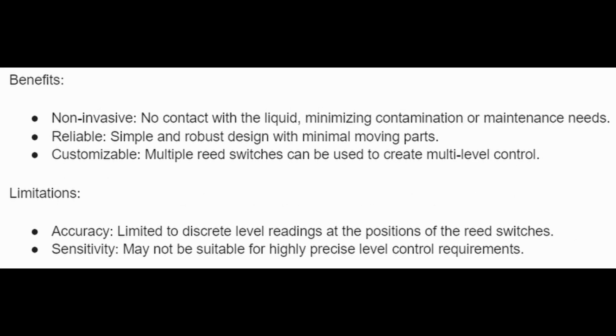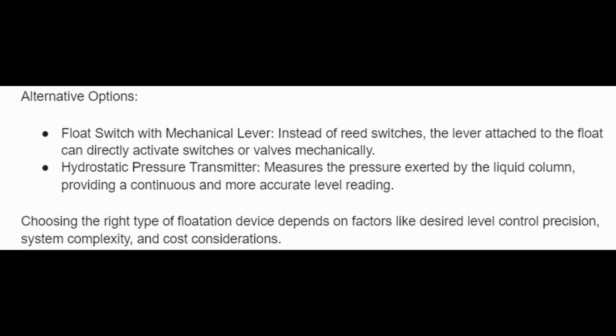Benefits: it's non-invasive, with no contact with the liquid, minimizing contamination or maintenance needs. Reliable, simple and robust design with minimal moving parts. Customizable, as multiple reed switches can be used to create multi-level control. Limitations: accuracy is limited to discrete level readings at the position of the reed switches. Sensitivity, it may not be suitable for highly precise level control requirements. Choosing the right type of flotation device depends on factors like desired level control precision, system complexity, and cost considerations.